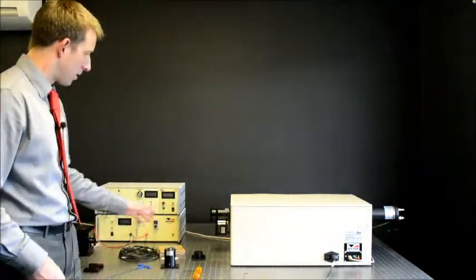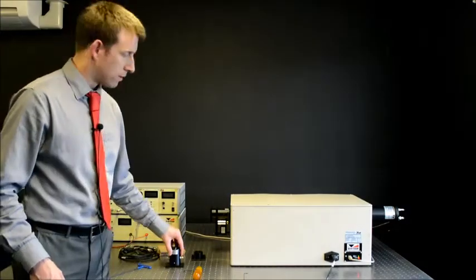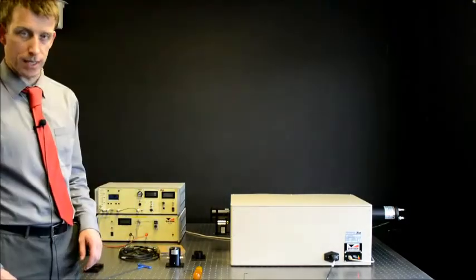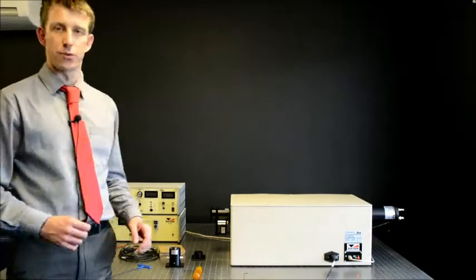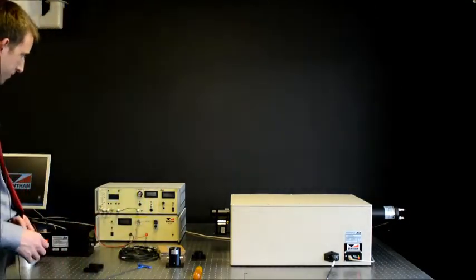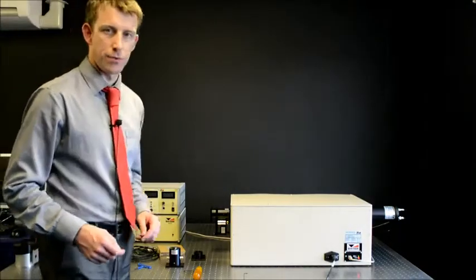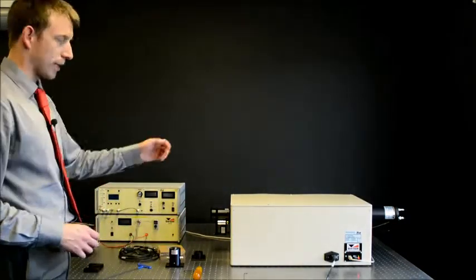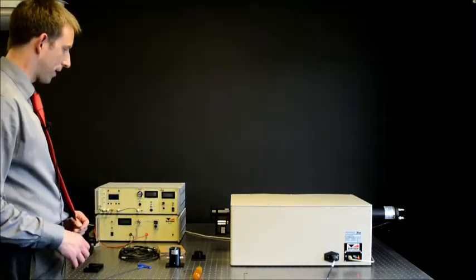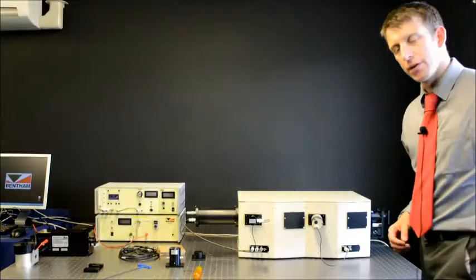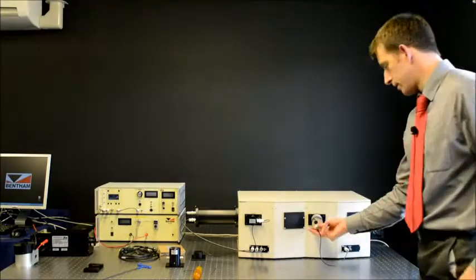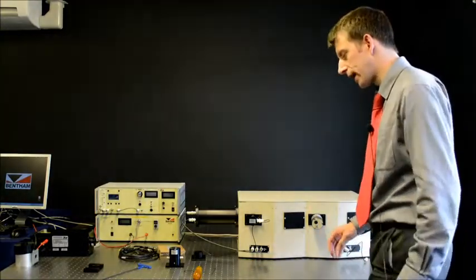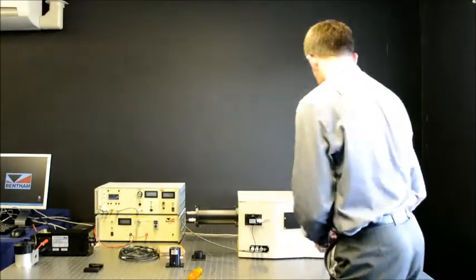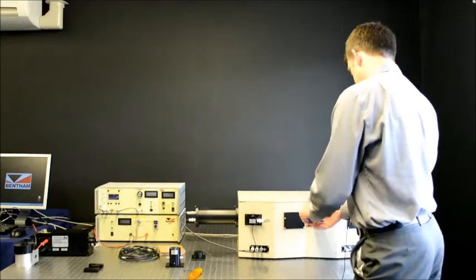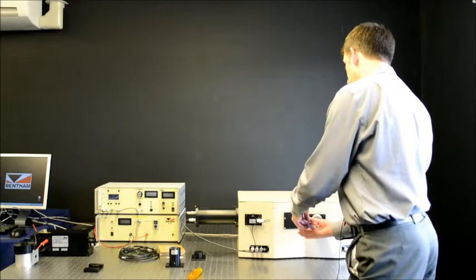We need now change the detector, the InGaAs detector for the lead sulfide detector, and we need also set up the detection electronics. I will turn round the IDR 300 so we can get a better view of the changes that need to be effected, and then we can start performing measurements. Now I've turned round the IDR 300, we can simply disconnect the signal cable from the InGaAs photodiode and remove the said photodiode from the exit of the first monochromator.